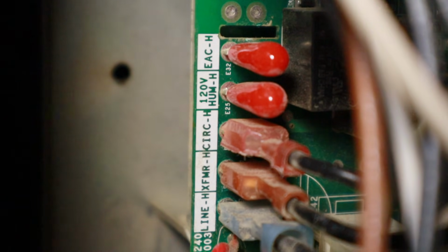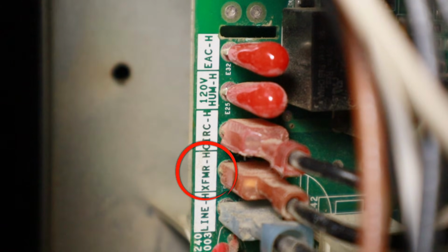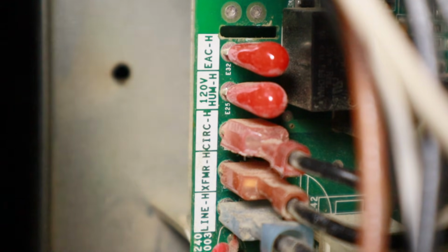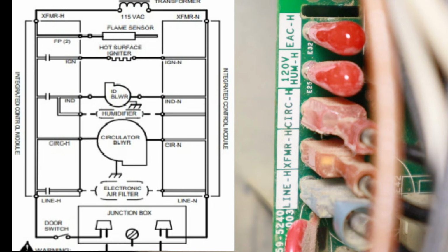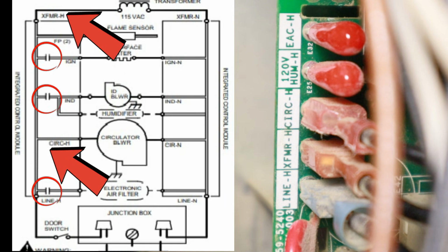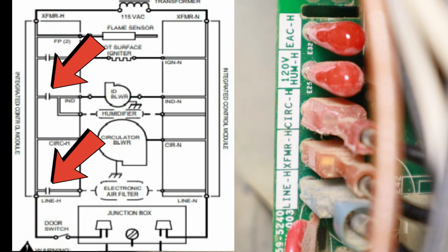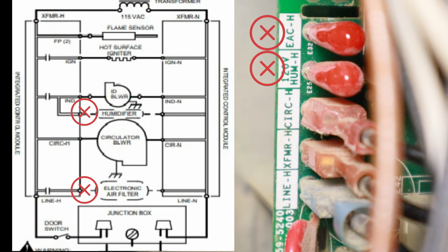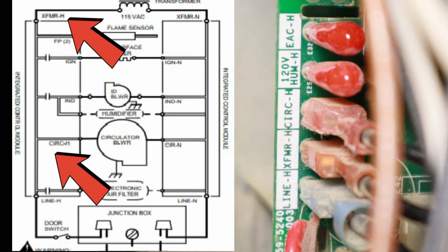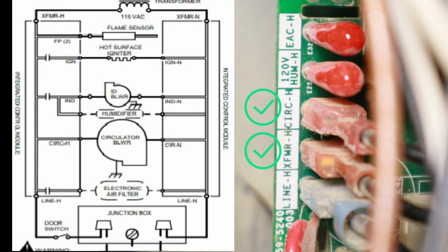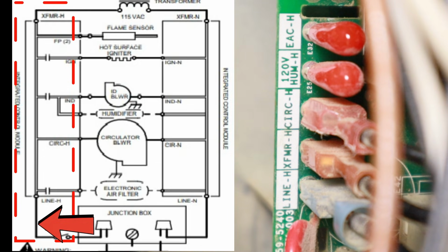Now you can see right above those terminals, we have transformer H and circ H. What that is, the transformer, that is our 120 to 24 volt transformer, and the circ H is actually for the circulation blower right there. So when we go to the ladder diagram, there's something I want you to take notice of. Some of these circuits off of this line voltage have switches in them and some don't. So basically what that's telling you is that if it has a switch in there, you're not going to read 120 volts off that terminal right now. Whereas if it doesn't have a switch there, you should read 120 volts on those terminal blocks because they're connected to the line voltage without any interruption in between.